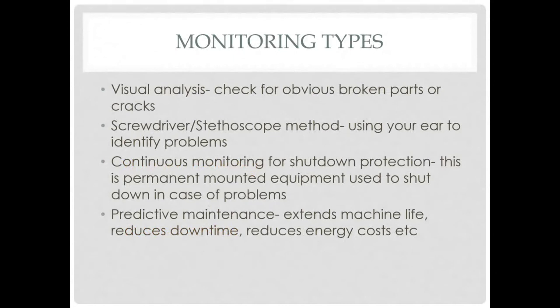Different monitoring types include visual analysis — checking for obvious broken parts or cracks — and the old screwdriver stethoscope method: put the handle against your ear, touch the other end to different parts of a motor, and it amplifies localized sounds to help determine where problems are. Continuous monitoring is used for shutdown protection — permanently mounted to equipment to shut it down in case of problems — and also strongly used for predictive maintenance to extend machine life, reduce downtime, and reduce energy costs.